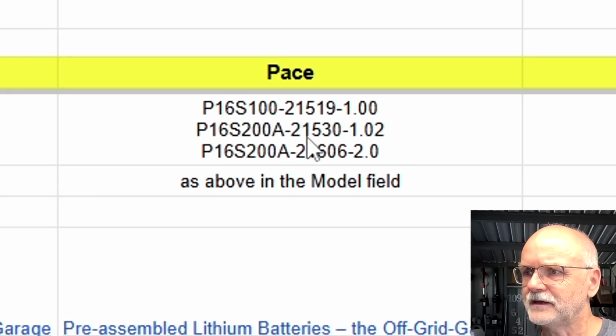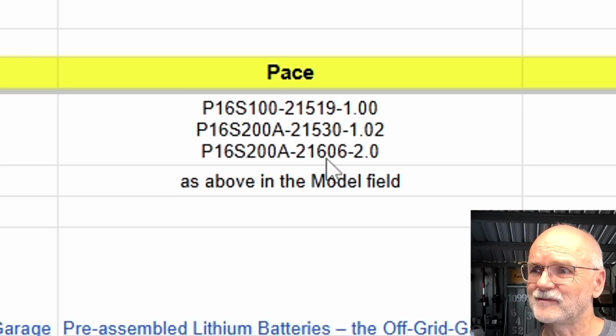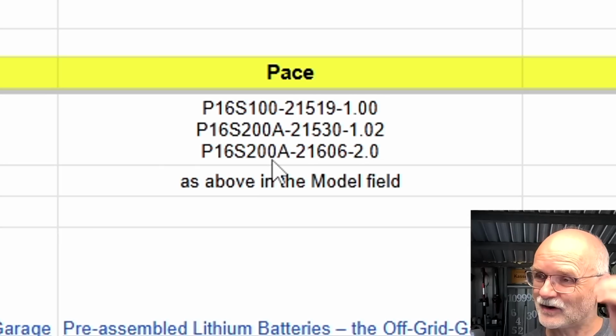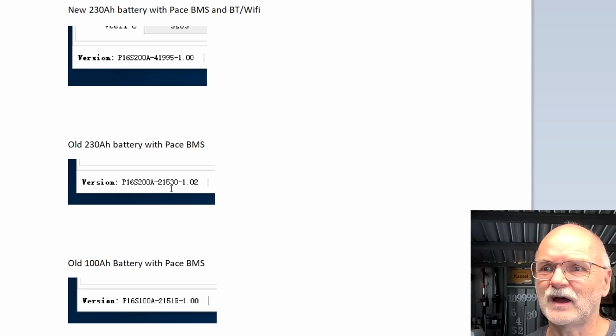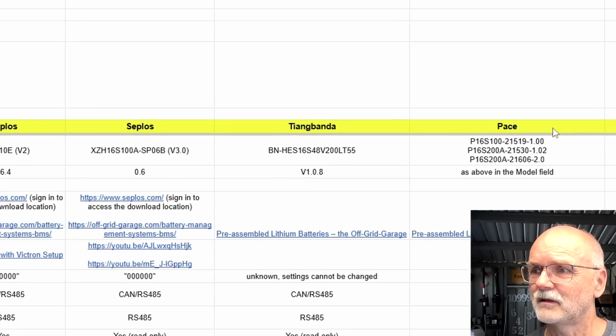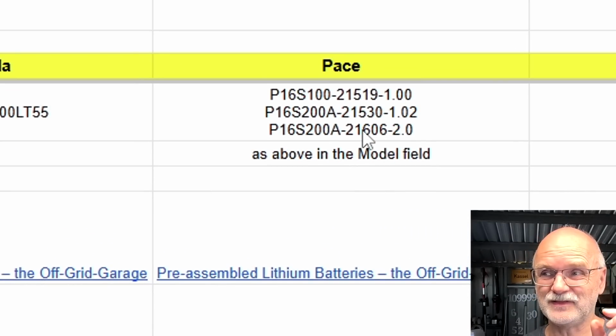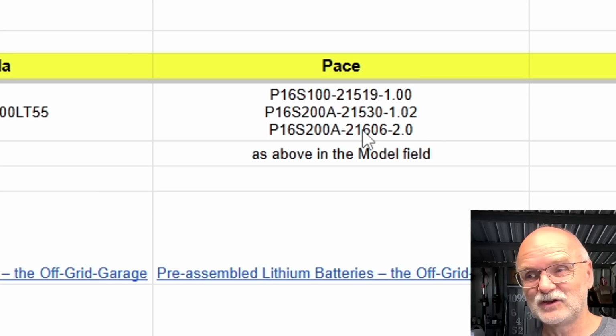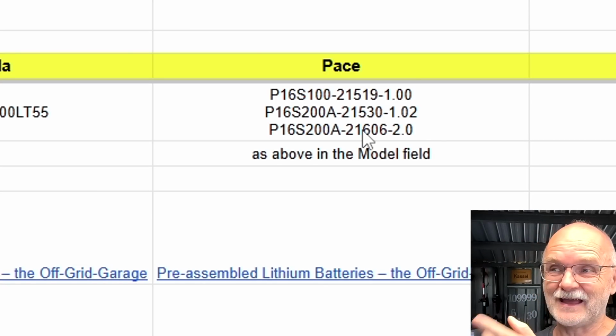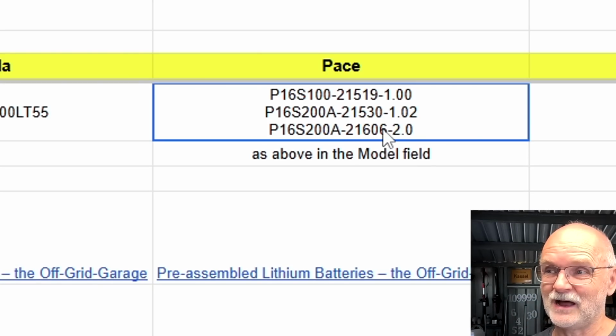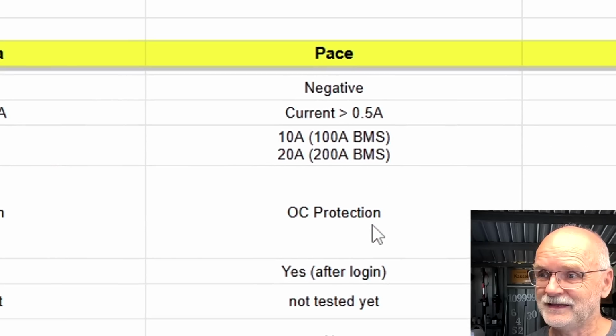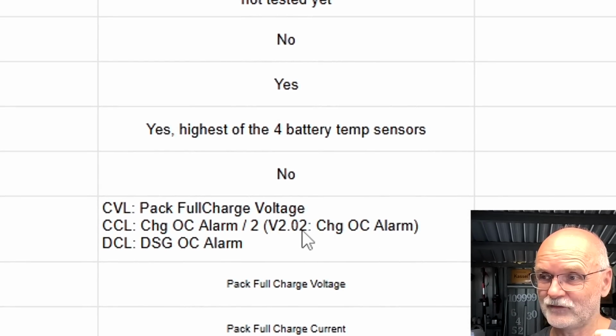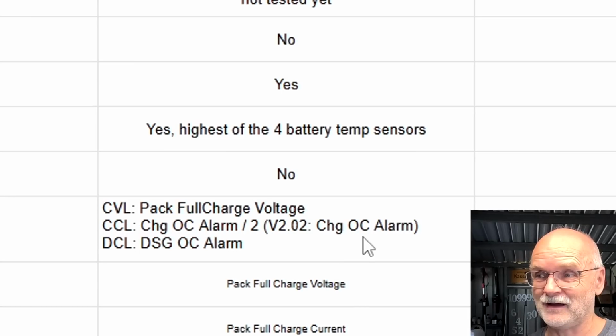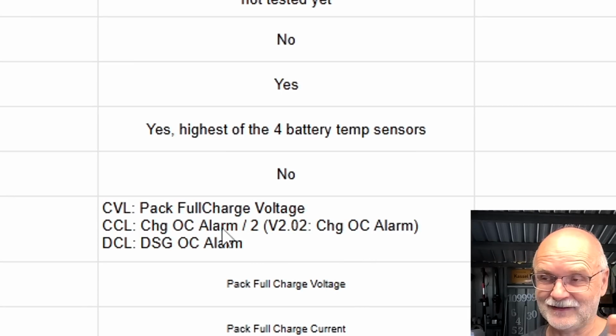What does it say here? On the PC, we've got actually a newer software for one of the BMSs. This is a 216, it's a different model again. P16S200, that might be 200, 530. 530, this is the one. Okay, this might be the actual Pace BMS that Gobel Power sent me way back in the day, because they were changing from a Gobel Power BMS to the Pace BMS in their pre-assembled batteries. And I did all the testing for the Pace BMS, and this seems to be a newer hardware version with firmware 2.0. And here in the list we can see version 2.0 of the firmware is actually using the charge over current alarm, not divided by 2 as in the other BMSs.